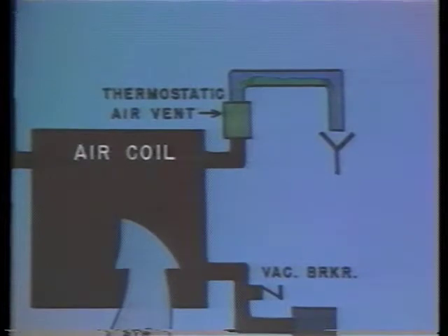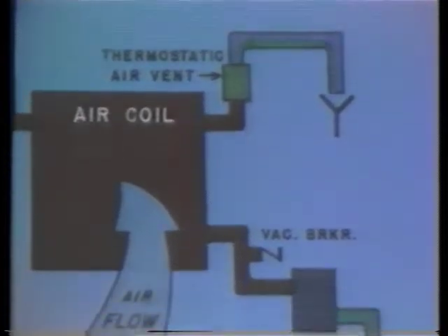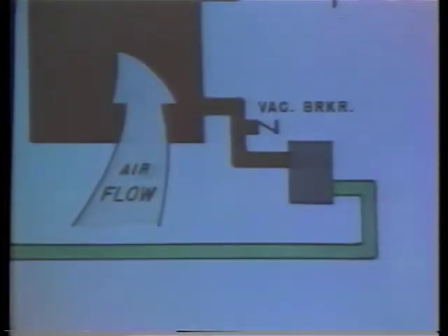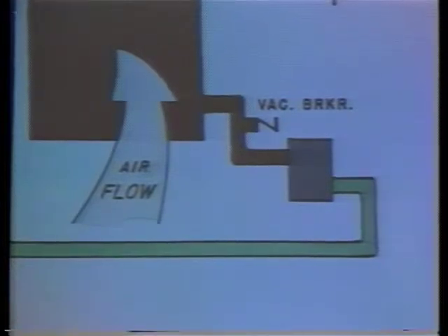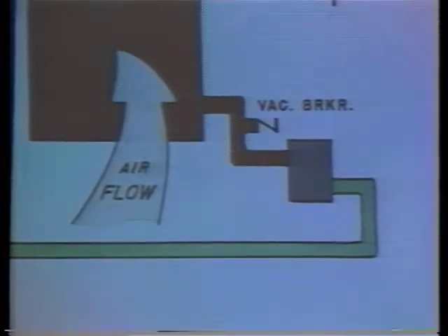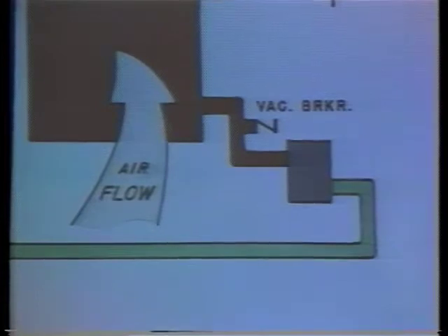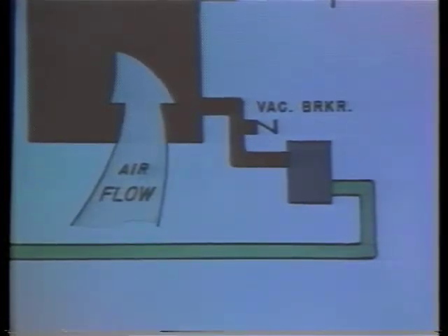On any of these types of coils, the operating characteristics of the inverted bucket trap can be very beneficial. The intermittent discharge causes momentary pressure surges, which continuously purges air and condensate from the coils. This condensate drainage system will make a high heat transfer efficiency possible, which, of course, can lead to higher production.